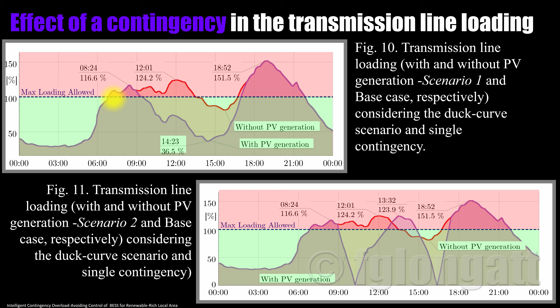And what we are doing is something very interesting. We are allowing the battery to charge during the sunlight hours, reducing the power that is exported from the PV rich area. But this power will be later used for 2 different conditions. During the night hours, that power can be sold to the local customers, reducing the loading of the transmission line during the night. But at the same time, during a contingency, I have room to charge the battery, and as a consequence, I can reduce the overloading.